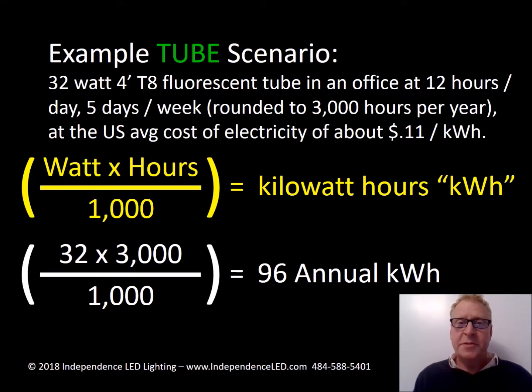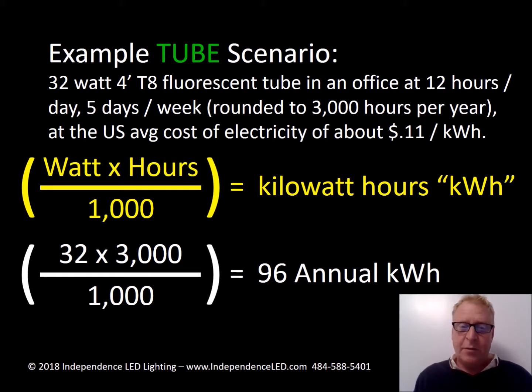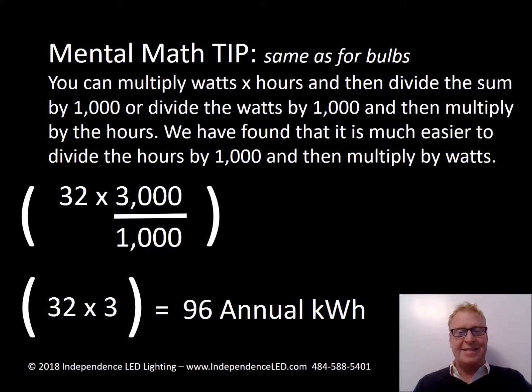Here's an example tube scenario: a 32 watt, very common four-foot T8 fluorescent tube — over two billion on American ceilings. At 12 hours in an office per day, five days per week, rounded to 3,000 hours. 32 watts times 3,000 divided by 1,000 equals 96 kilowatt hours. This is that same mental math tip where dividing the 1,000 into the hours versus the total sum makes it much faster.